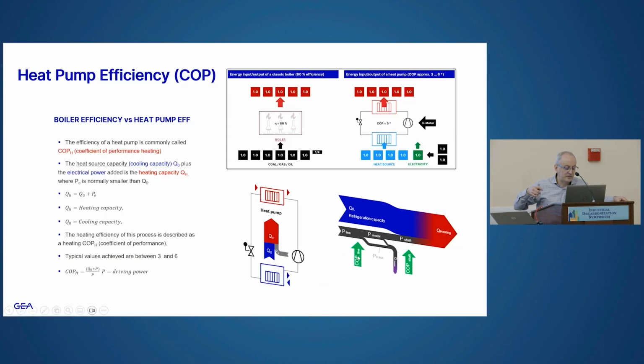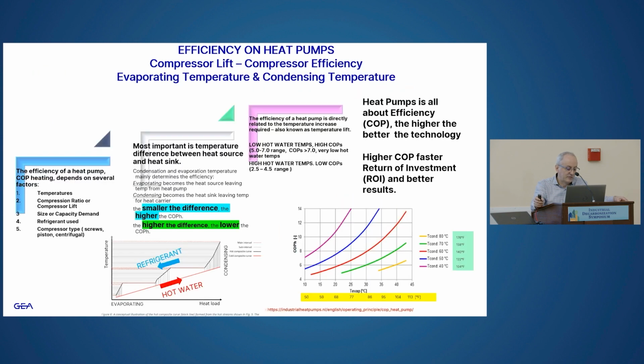And COP line. That's because we start adding any motor losses, any variable frequency drive losses, or any losses that are also part of the heat pump efficiency. So the efficiency is going to be driven by your temperature lift. The higher the temperature lift, the less efficient the heat pump. It's going to be a low COP. The smaller that temperature lift, the higher that COP. So if you have temperatures around 140 F water, yeah, great, you're going to get a great COP. But if you want 190 F or 200 F water, you're going to have a small COP.